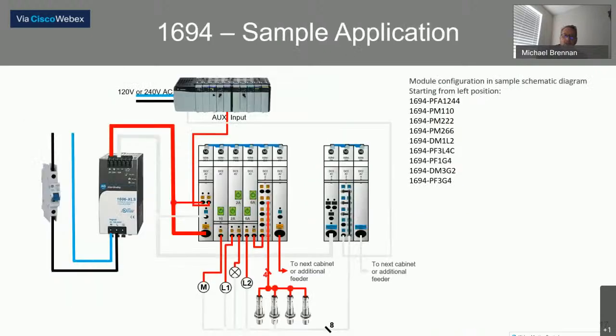So here's an example of an application as it's put together. This specific application has 5 circuits. So in a 10 or 11 circuit application, it could be just a little bit bigger than this. And you can see we've got power feed modules as well as the individual protection modules. And this gives us the ability then to route between different panels. So we can have one up to 40 amp supply, and we can provide individual circuit protection as well as class 2 protection where required.